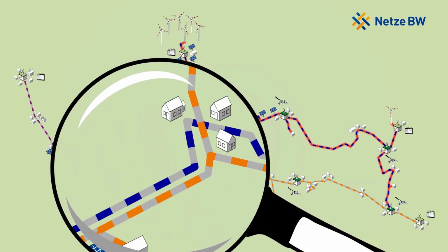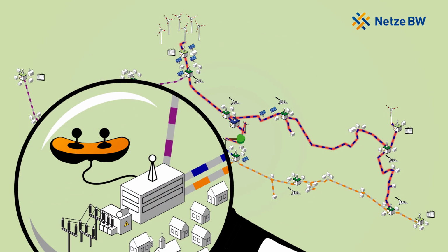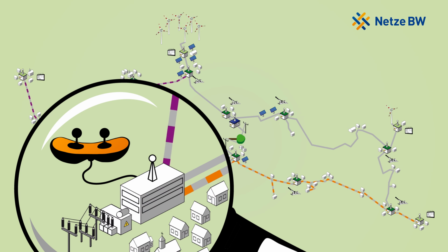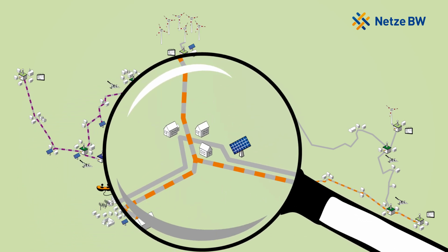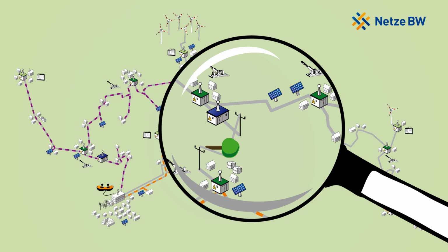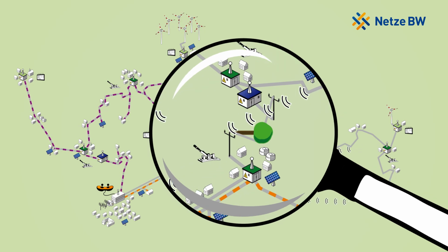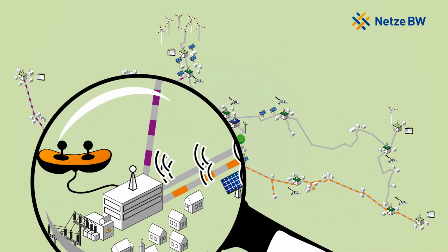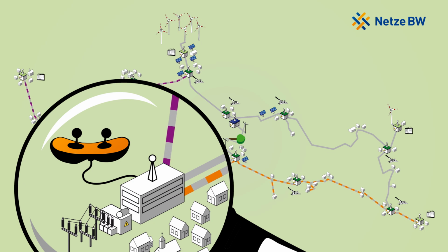In the event of an outage, the entire medium voltage line is still shut down like before. However, thanks to the information from the intelligent distribution substations, the controller can locate the fault with high precision. It calculates within a matter of seconds the optimum grid configuration for isolating the fault and quickly restoring supply to as many customers as possible.